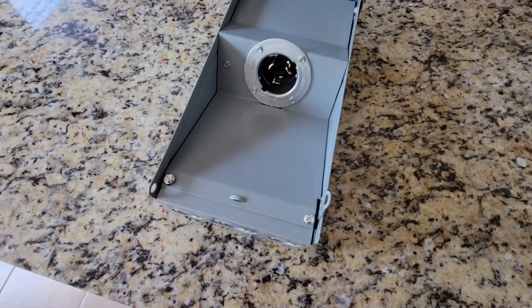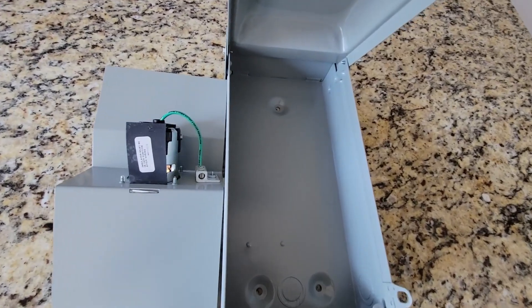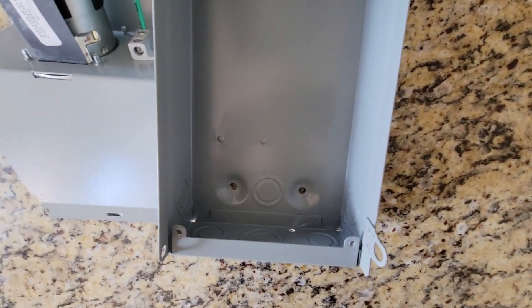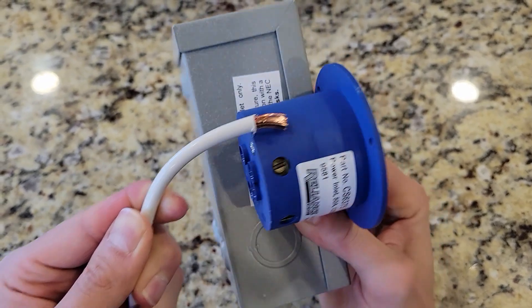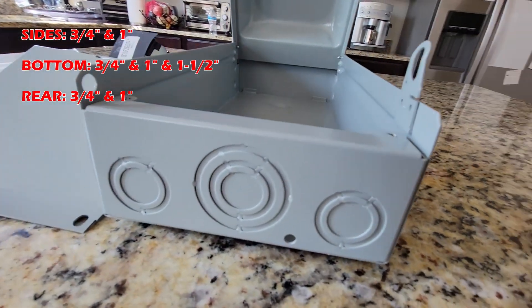Inside, there are two screws that give you access to the back of the receptacle. This enclosure has plenty of space for the wires to bend and be installed easily. This is fantastic, as many competitors provide tiny enclosures that violate wire bending space requirements — for example, this one. There are also conduit knockouts on all sides for convenience.